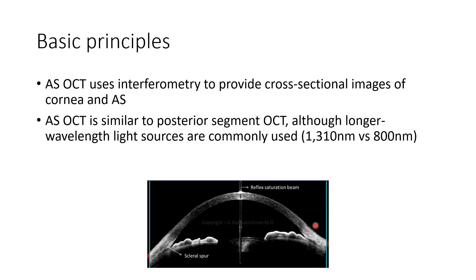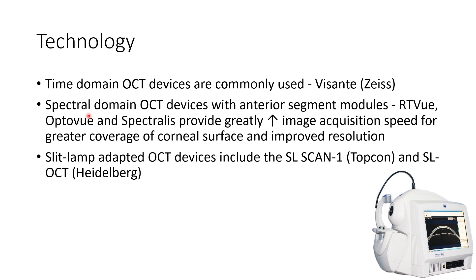This picture shows an ASOCT image of a normal eye. Regarding technology in ASOCT, time domain OCT devices are commonly used — an example being Visante by Zeiss. Spectral domain OCT devices with anterior segment modules, such as RTVue, OptoVue, and Spectralis, provide greatly increased image acquisition speed for greater coverage of the corneal surface and improved resolution. Slit lamp adapted OCT devices include the SL-Scan1 by Topcon and SL-OCT by Heidelberg. This picture shows Visante, which is an ASOCT device.